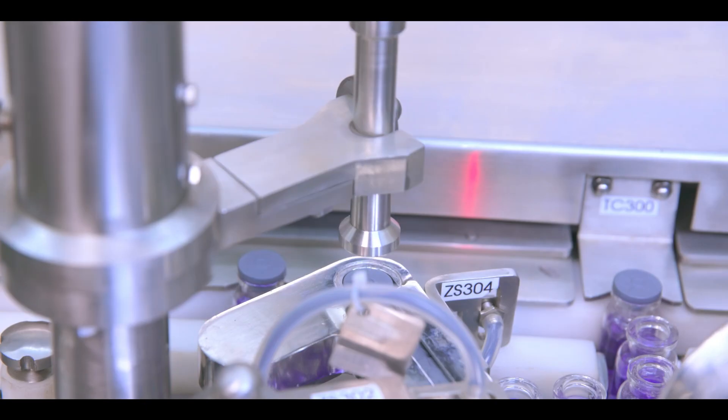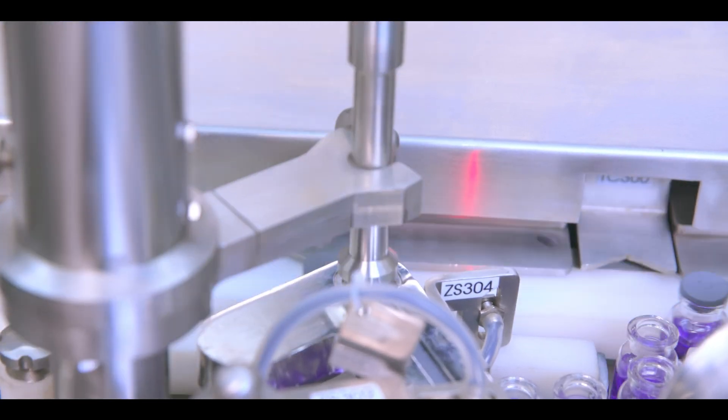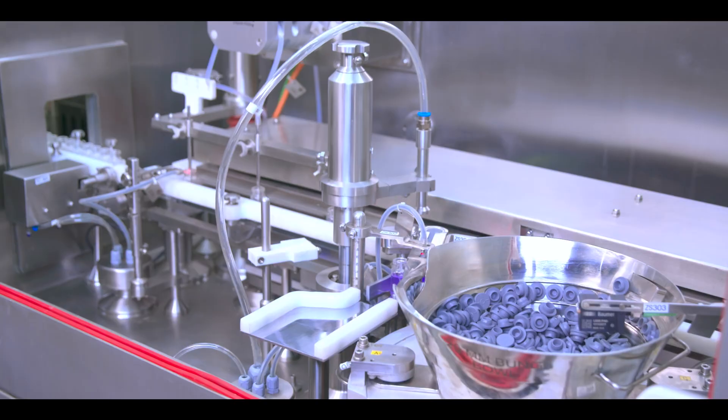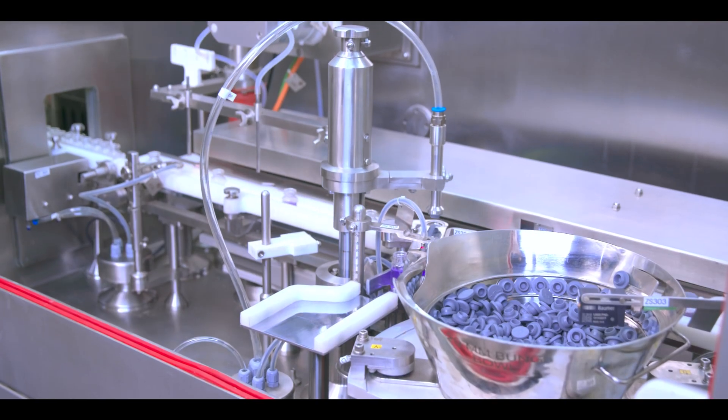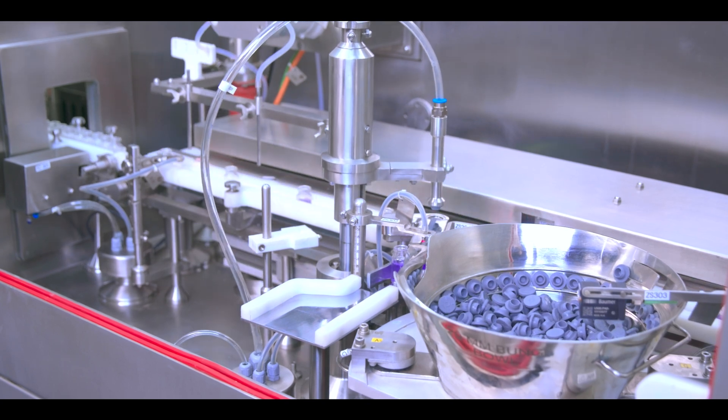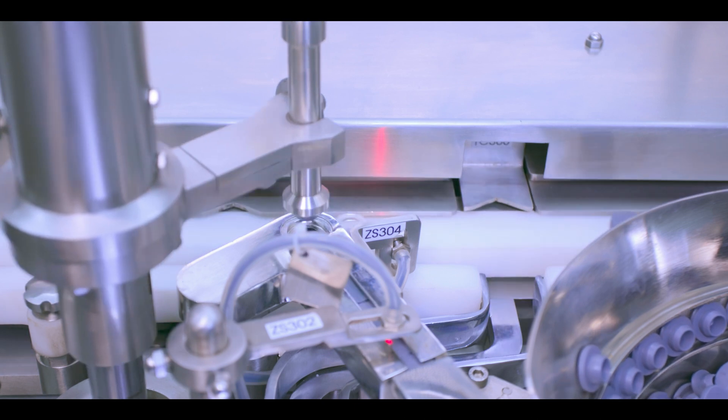Vials are stoppered by a pick and place mechanism. The stoppers are fed through rapid transfer port, and the rejection system removes unstopped vials.